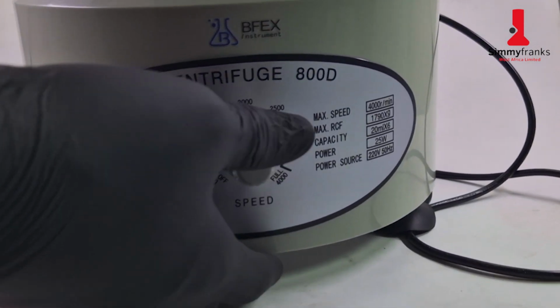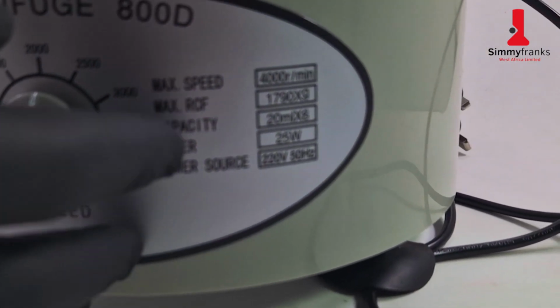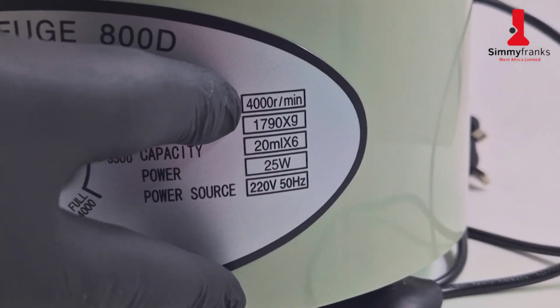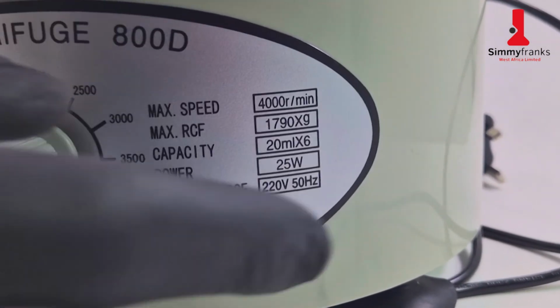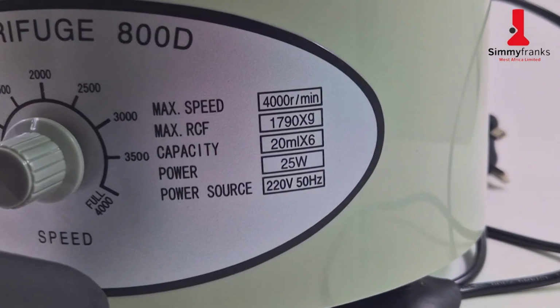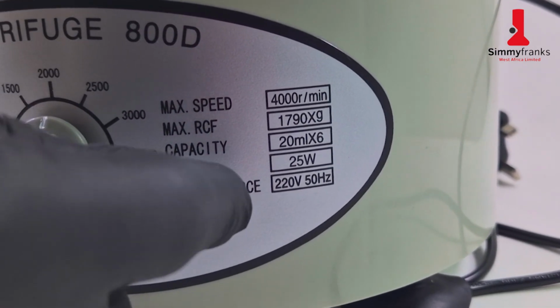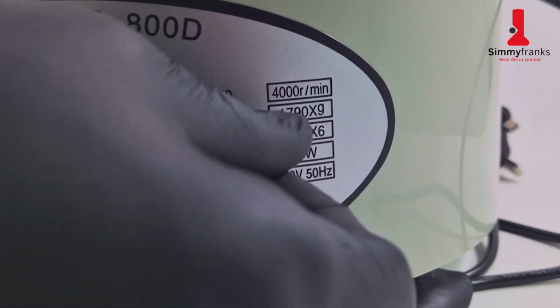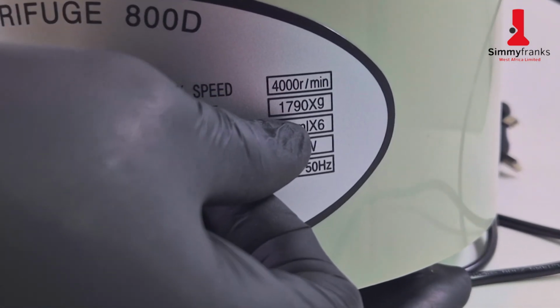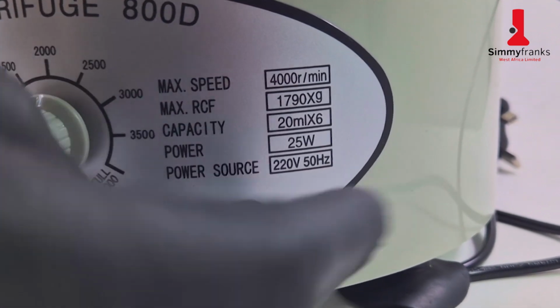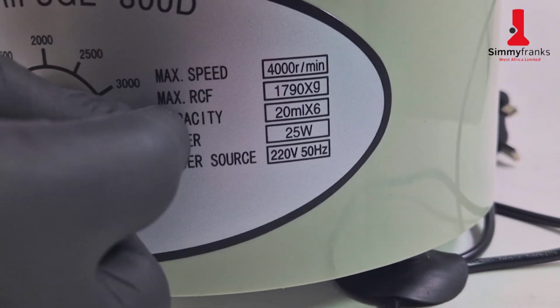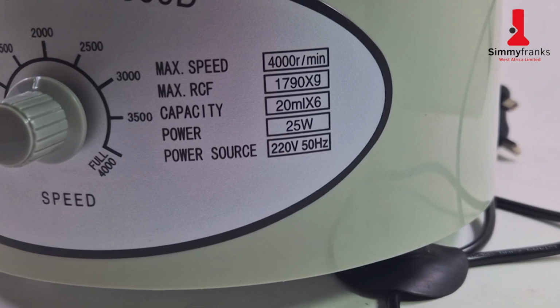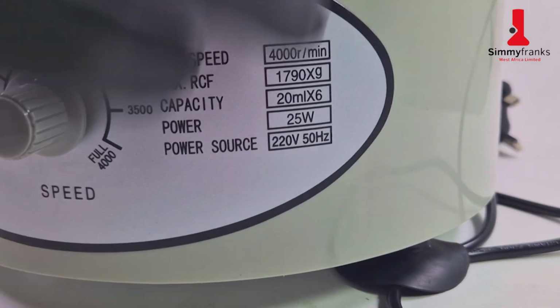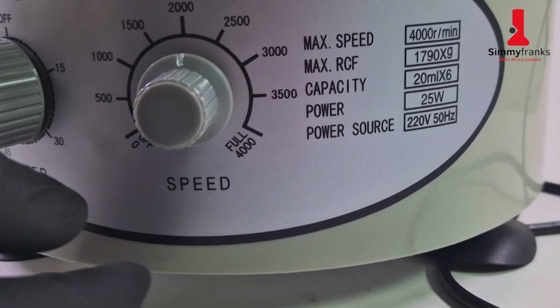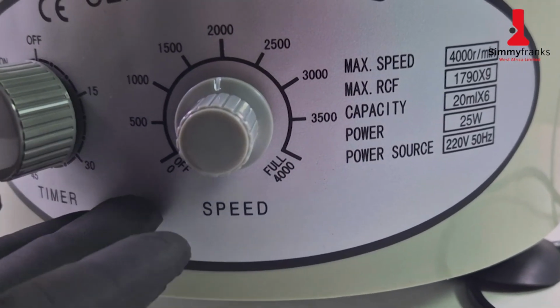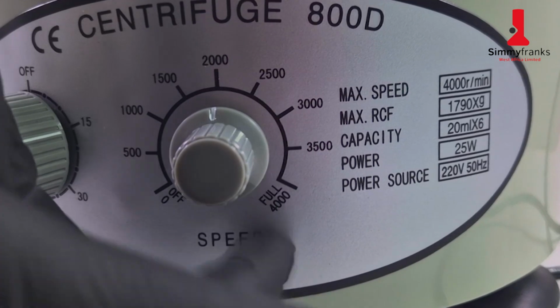So here is the spec of this particular centrifuge. It has a revolution of 4,000 revolutions per minute. So that's the maximum speed, and also the relative gravity is 1,790 g, and also the capacity for each of the centrifuge tubes you can use is 20 mils, and we have 6 of them.